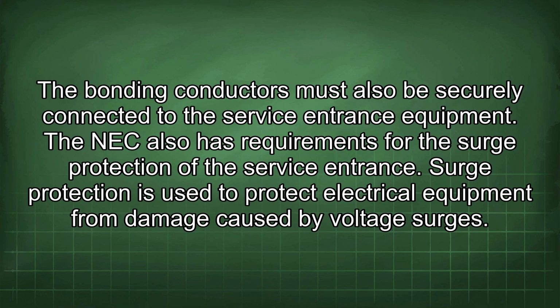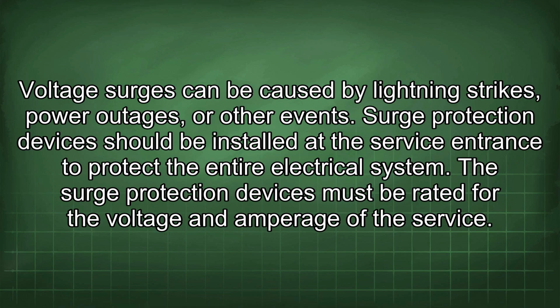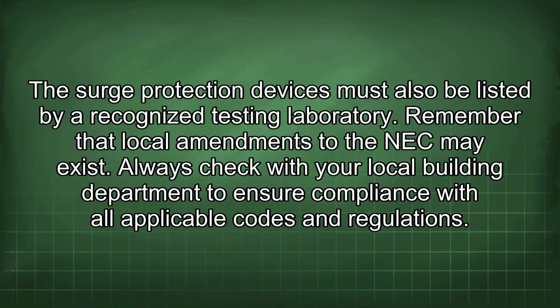The NEC also has requirements for the surge protection of the service entrance. Surge protection is used to protect electrical equipment from damage caused by voltage surges. Voltage surges can be caused by lightning strikes, power outages, or other events. Surge protection devices should be installed at the service entrance to protect the entire electrical system. The surge protection devices must be rated for the voltage and amperage of the service. The surge protection devices must also be listed by a recognized testing laboratory.